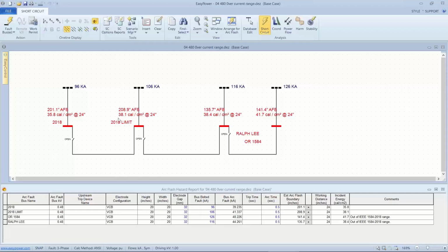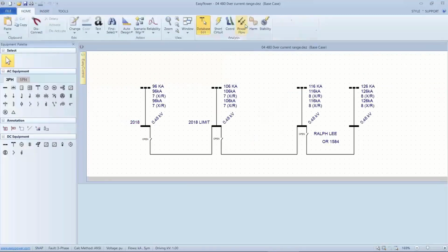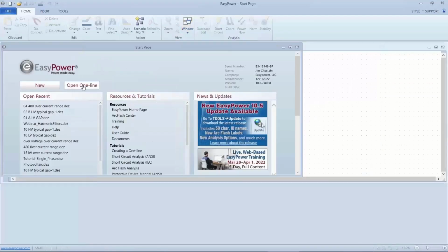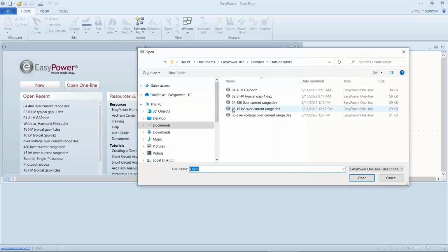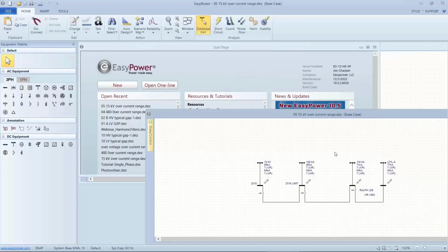And so I'm feeling comfortable using the calculations when I'm slightly beyond the limit, for both a 10% difference and a 20% difference. It's just me. So let's try holding a higher voltage, doing the current range at a higher voltage. So I want to go to the start page. I want to go to 15 kV overcurrent. Same type of setup.